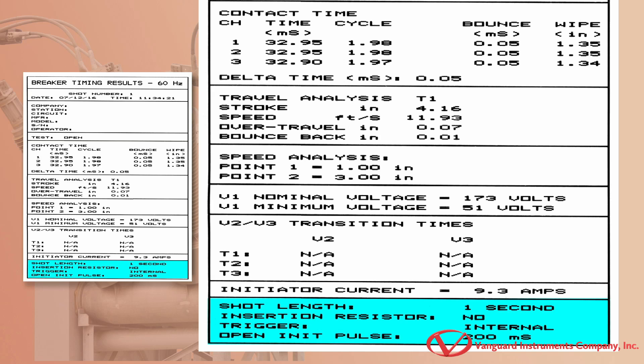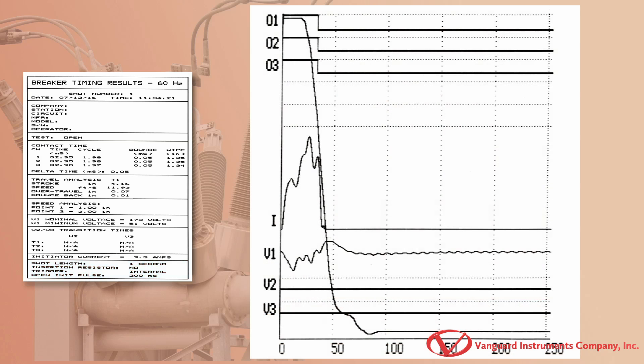This last section shows additional test information. We can see that the shot duration was one second, there was no insertion resistor in the circuit breaker under test, and the trigger mode was set for internal trigger. Lastly, here is the graphical printout of the test results.